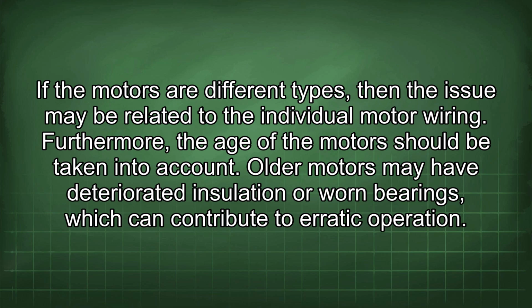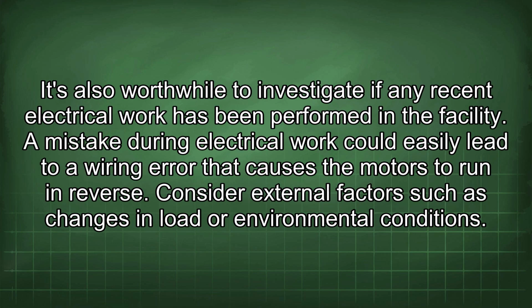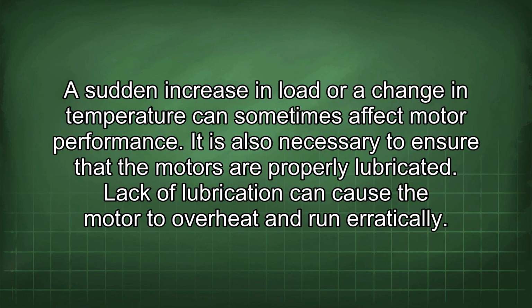Furthermore, the age of the motors should be taken into account. Older motors may have deteriorated insulation or worn bearings, which can contribute to erratic operation. It's also worthwhile to investigate if any recent electrical work has been performed in the facility. A mistake during electrical work could easily lead to a wiring error that causes the motors to run in reverse. Consider external factors such as changes in load or environmental conditions. A sudden increase in load or a change in temperature can sometimes affect motor performance.